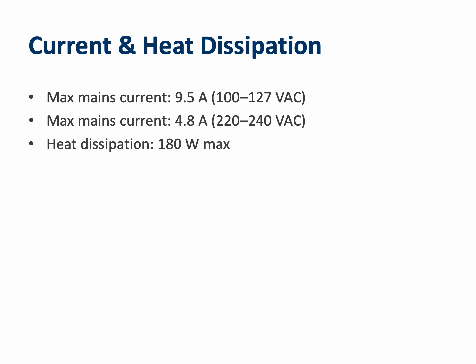Looking at current draw, the FT10 consumes up to 9.5 amps at lower voltages and about 4.8 amps at higher voltages. This is well within the limits of hospital-grade outlets, but still requires awareness to avoid tripping breakers. Another important figure is heat dissipation, up to 180 watts. This tells us that the unit will give off a noticeable amount of heat during use, reinforcing the need for good airflow around the machine and avoiding enclosed or poorly ventilated storage.